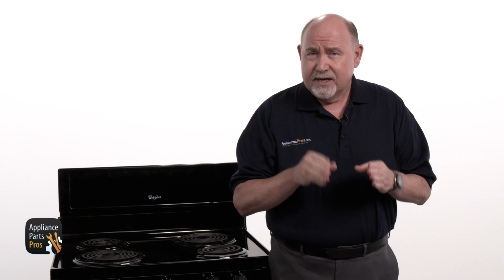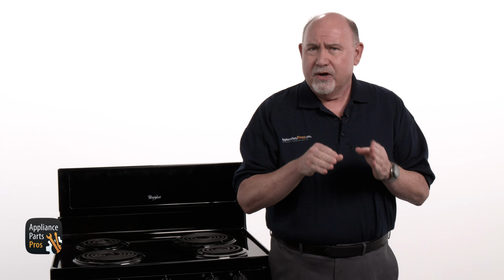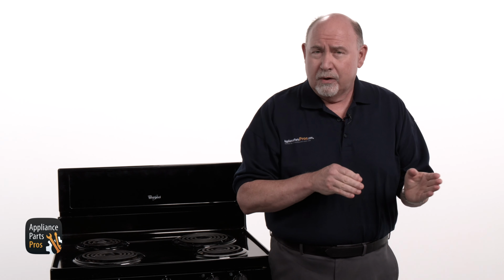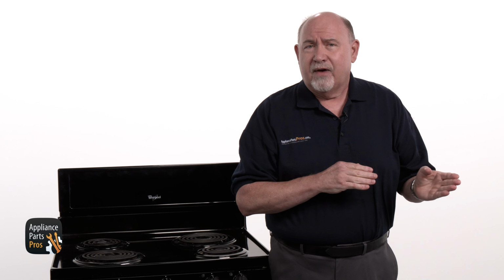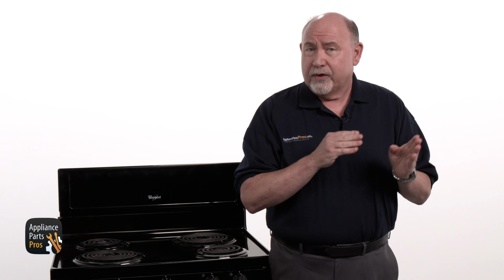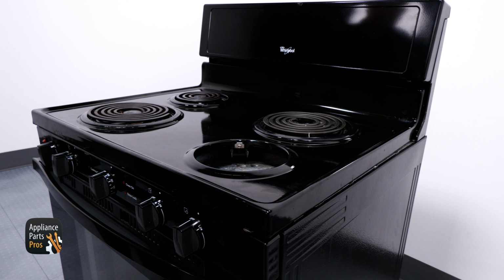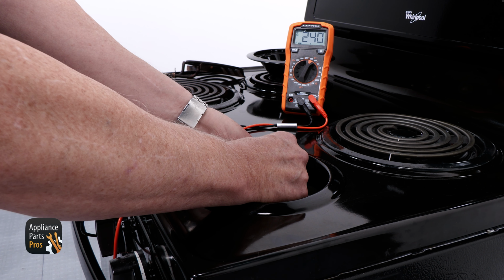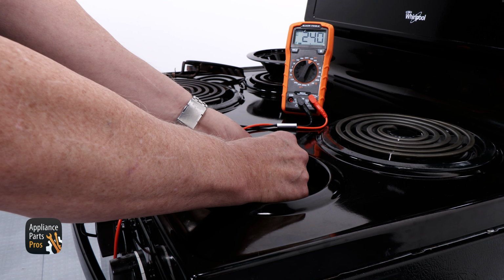If the voltage isn't correct, there's either incorrect voltage going to the switch, or the switch is defective and not sending the right amount of voltage to the element. If the other elements are working, then there is most likely a problem with the switch. If the switch is good, we can move on to test the element.